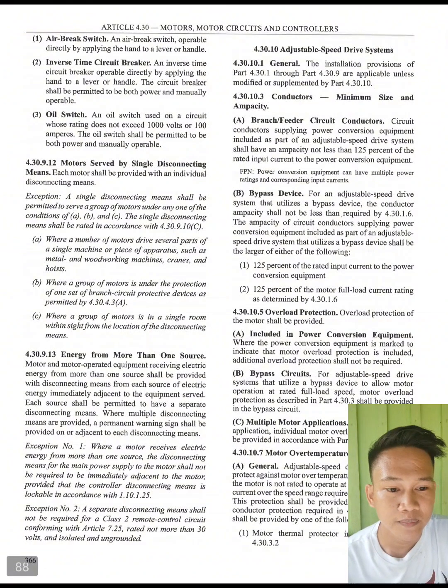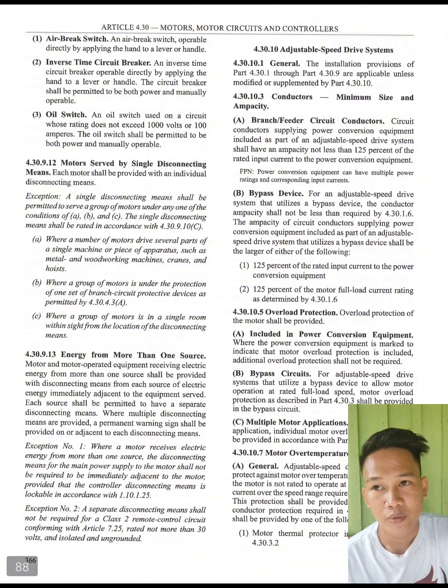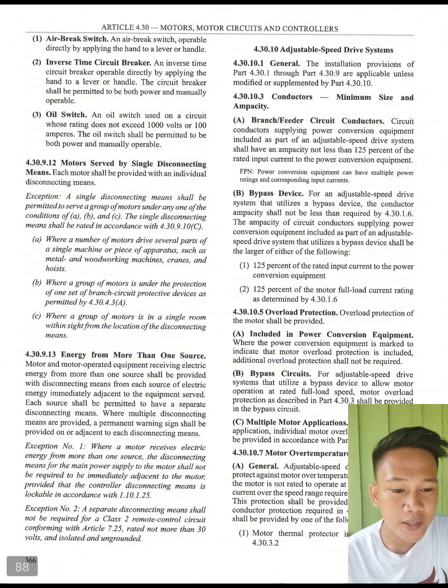Next, we have 4.30.10.5. Overload protection. Overload protection of the motor shall be provided. A. Included in power conversion equipment. So, where the power conversion equipment is marked to indicate that motor overload protection is included, additional overload protection shall not be required. So, second, bypass circuits. B. For adjustable speed drive system that utilize a bypass device to allow motor operation at rated full load speed, motor overload protection as described in part 4.30.3 shall be provided in the bypass circuit. Next, C. Multiple motor application. For multiple motor application, individual motor overload protection shall be provided in accordance with part 4.30.3.